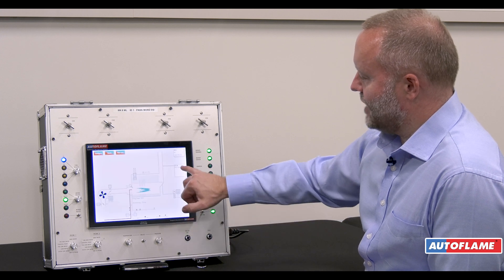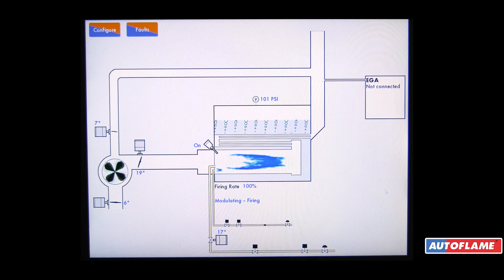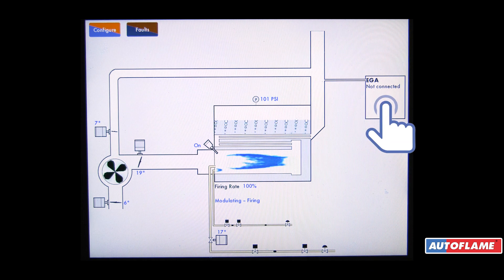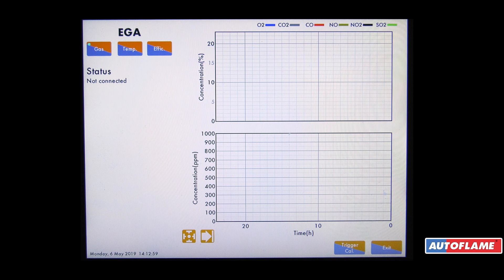Now if we have an exhaust gas analyzer, the Autoflame exhaust gas analyzer connected to the system, we get this additional box. By pressing on this box it will show us the oxygen, CO2, CO, NO, NO2, and also the SO2 if we're burning heavy oil.